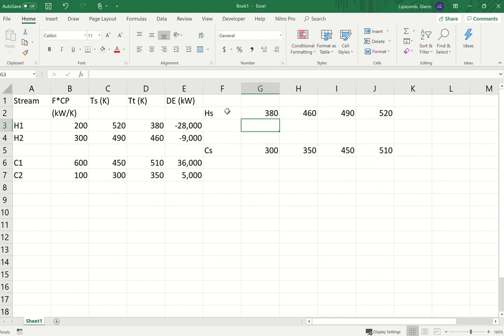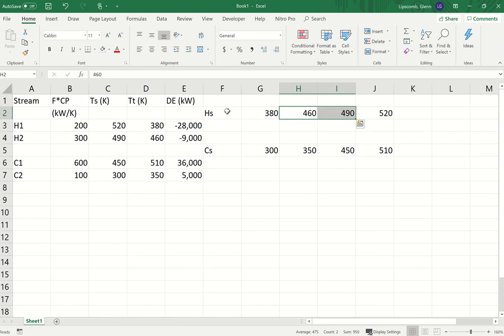In these two rows I'm going to calculate the heat exchange — the energy transfer — that occurs for heat exchanger one and heat exchanger two for intervals defined by the temperatures listed here. The first temperature interval is 380 to 460, the next is 460 to 490, and then 490 to 520. I'm going to enter a formula that will determine if there is heat transfer in each temperature interval for H1 and H2, calculate that value if there is, or put a zero if not.